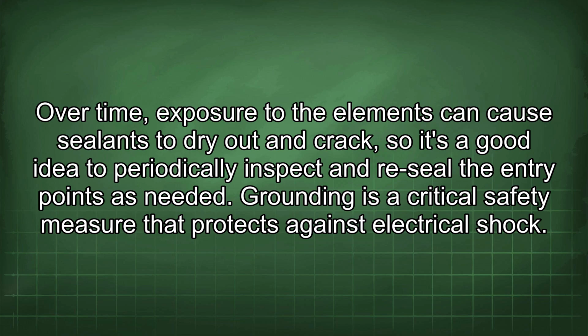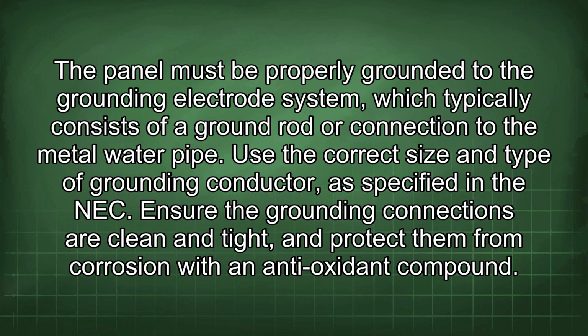Grounding is a critical safety measure that protects against electrical shock. The panel must be properly grounded to the grounding electrode system, which typically consists of a ground rod or connection to the metal water pipe. Use the correct size and type of grounding conductor as specified in the NEC. Ensure the grounding connections are clean and tight, and protect them from corrosion with an antioxidant compound.